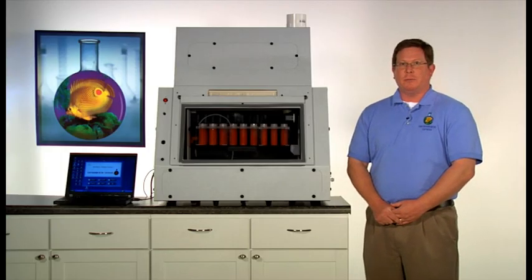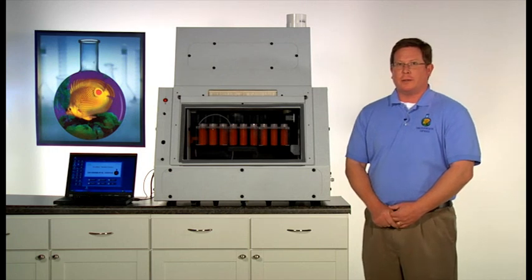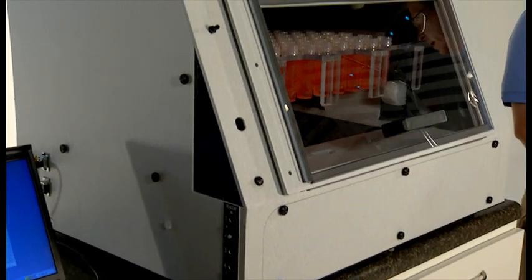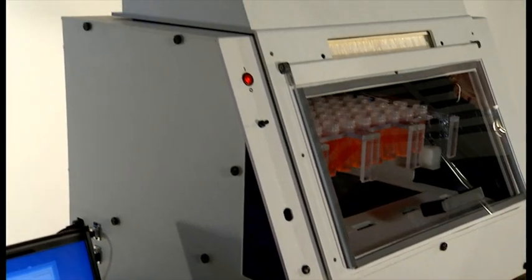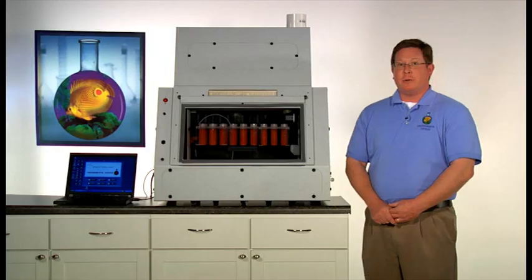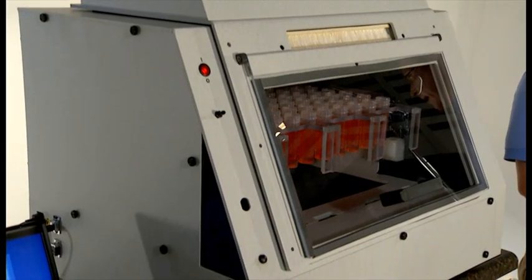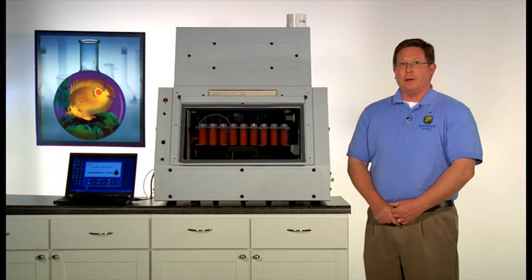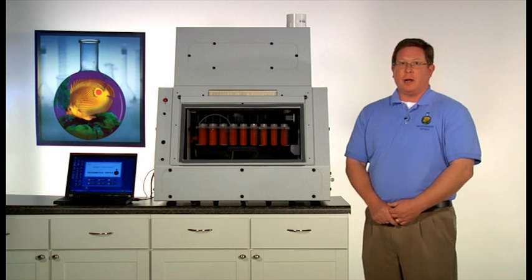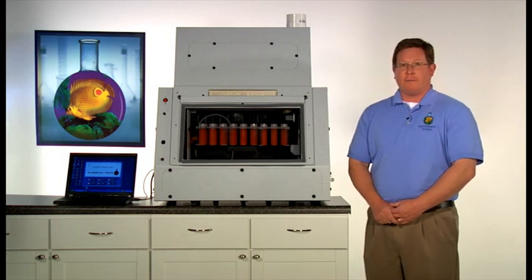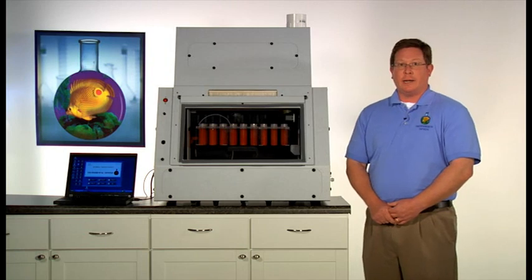My name is Joe, and today we'll be discussing metals digestions with the AutoBlock. The AutoBlock provides a fully automated metals digestions process, from injection of concentrated acids and reagents all the way to our final fill-to-volume step, which brings sample volume back to its original 50 milliliter volume by injecting deionized water into every vessel. The AutoBlock does all of this in a corrosion-free environment and utilizes a 54-well, 50 milliliter size heating block. The heating block is constructed of Teflon-coated graphite and is housed in a Kydex casement.